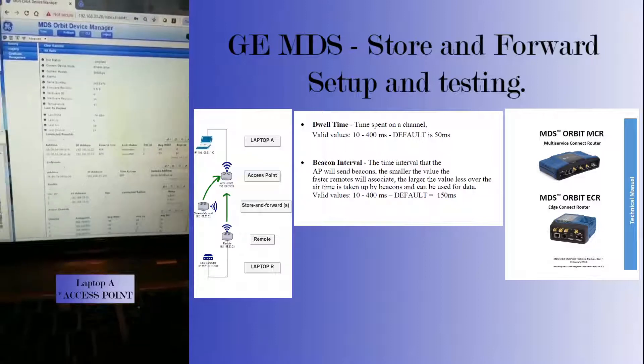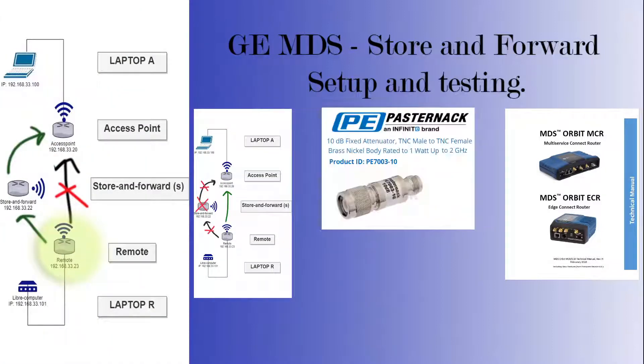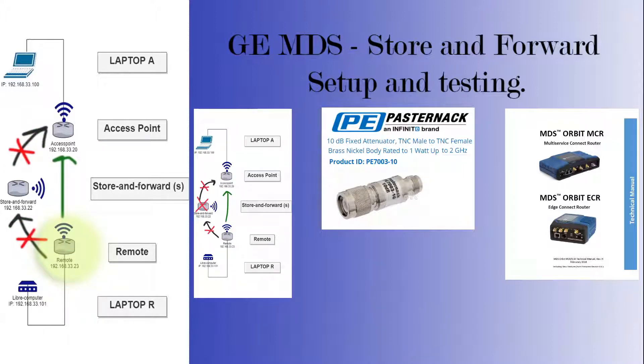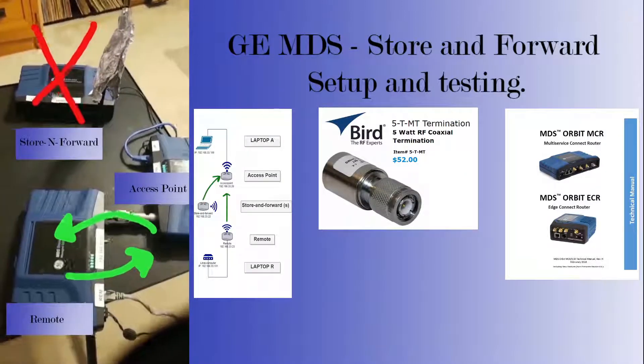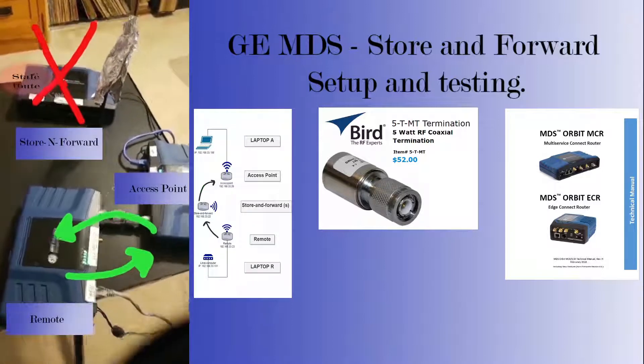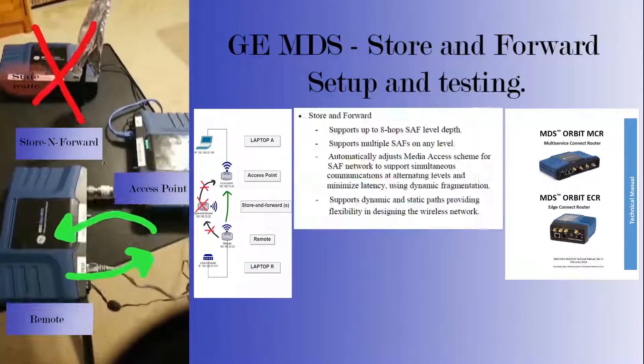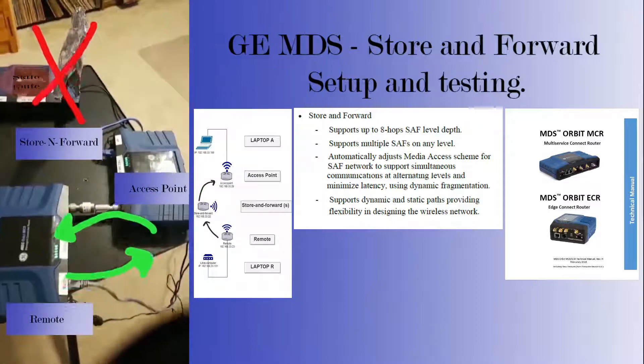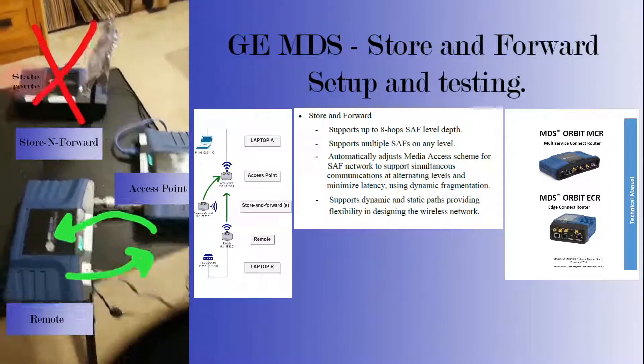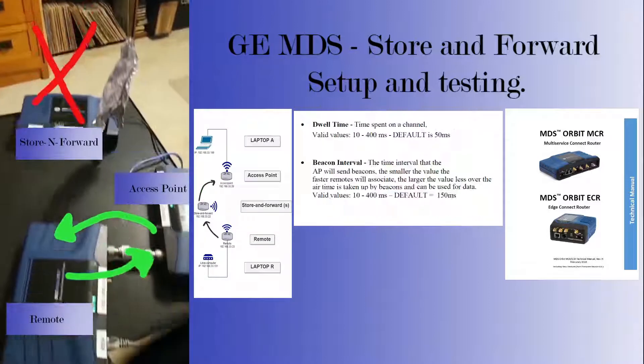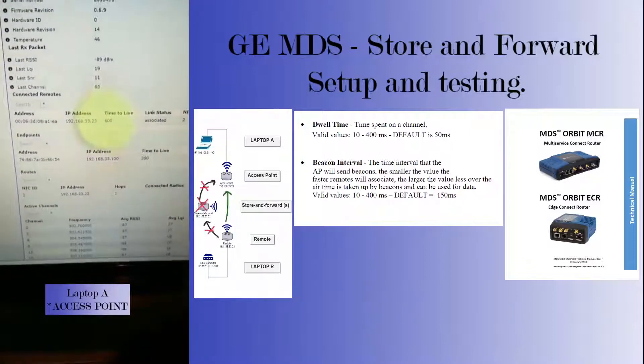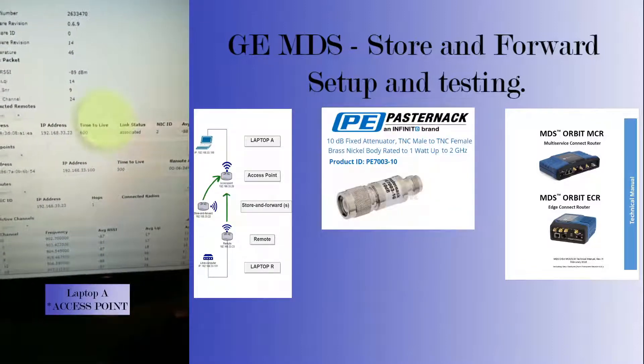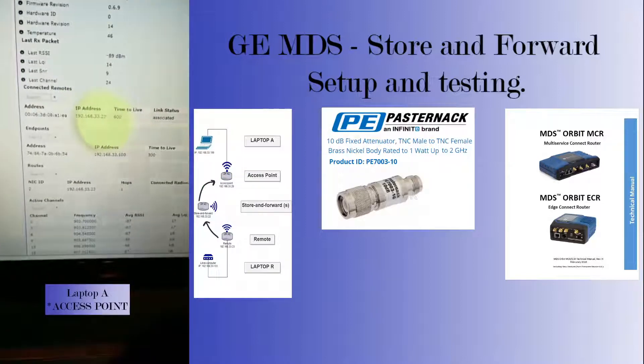Our remote that was talking through the store-and-forward is now talking directly to the access point, and we did nothing more than remove it from the picture. You may have noticed on the GUI that the store-and-forward — the .22 — was still listed. That was probably a stale entry in the sense that it wasn't actually active but was still in the table. Now we're going to turn it back on, and you can see that stale table entry did update and it's no longer listed. Our remote is still showing connected as one hop.